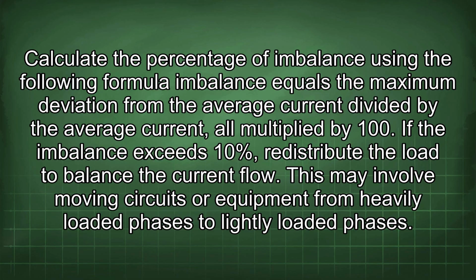If the imbalance exceeds 10%, redistribute the load to balance the current flow. This may involve moving circuits or equipment from heavily loaded phases to lightly loaded phases.